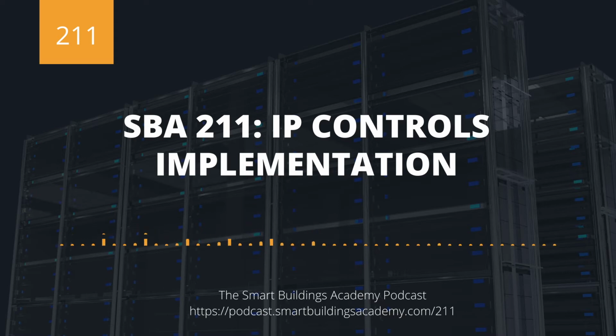We daisy chain from controller to controller, except instead of having a terminal block that we stick the wires in and then crank down our nuts on the wires to tighten them up, and then the wires are actually electrically bridged, right? They're physically connected. Unlike that, in a lot of controllers, they are logically bridged. What I mean by that is you have two network interface cards. One Ethernet wire comes into one, and then it leaves and goes to the other controller, and so on and so forth in a daisy chain pattern.